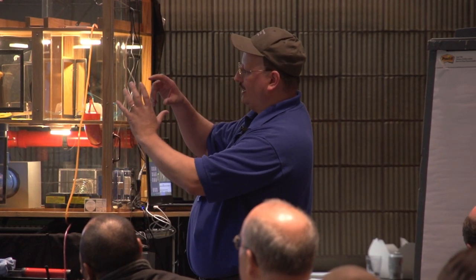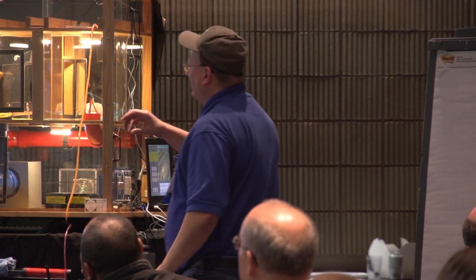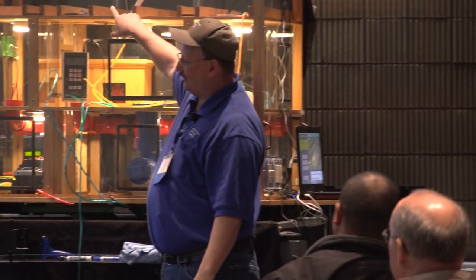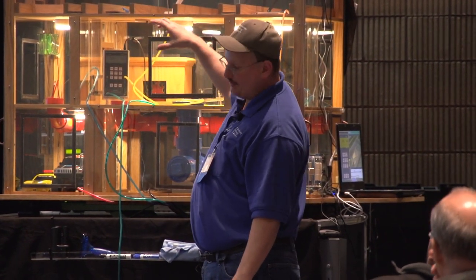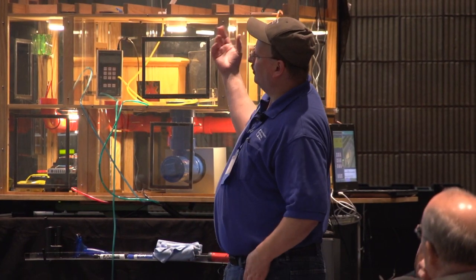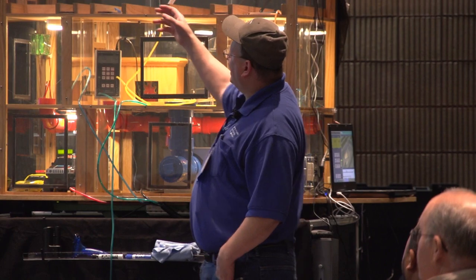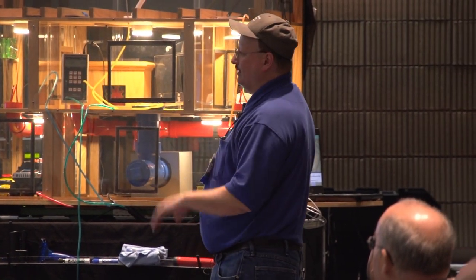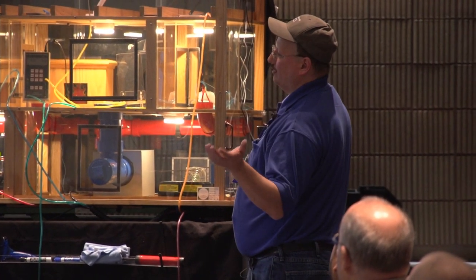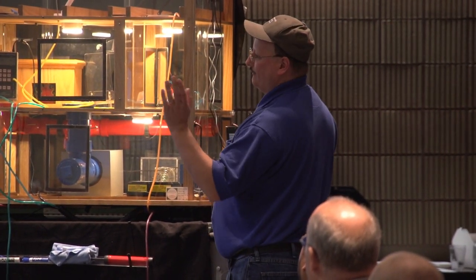We'll look at this chart again in the second part, but basically that tells me that the hole between the house and the attic is 1/8 of the hole between the attic and the outdoors. We'll talk about that and go through some examples. But that's usually not too bad. If I don't have a whole lot of attic venting, maybe less than 100 square inches, an eighth of that's not too big. But let's say I have huge amounts of venting. Would an eighth of that be a whole lot? Yeah. So sometimes that number could not be a good enough number if you have a lot of attic venting.